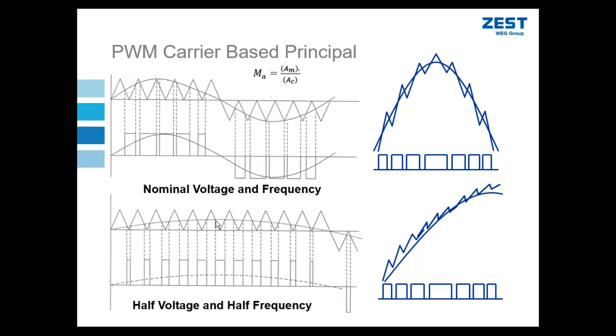When I reduce the output voltage to the motor and proportionally reduce the output frequency, in the second case here we can see that for one cycle, I'm only now doing half a waveform. So this is supplying 25 hertz to the motor. Because I'm only supplying 25 hertz, I decrease my sinusoidal waveform to half that of the carrier waveform. So in this case, my modulation index is said to be 0.5. Another interesting thing to point out between these two different waveforms, the switching frequency in both these cases is exactly the same. It's the same VSD. Its switching frequency is set to 600 hertz in this case.